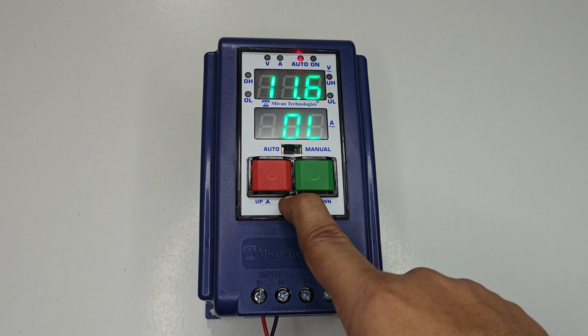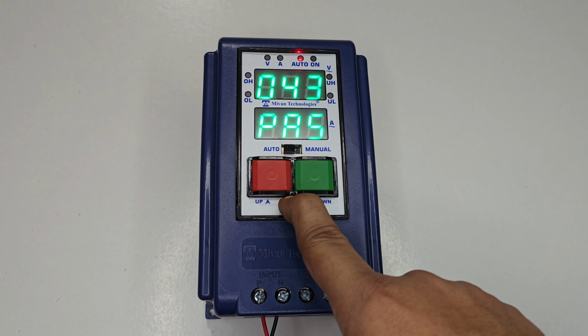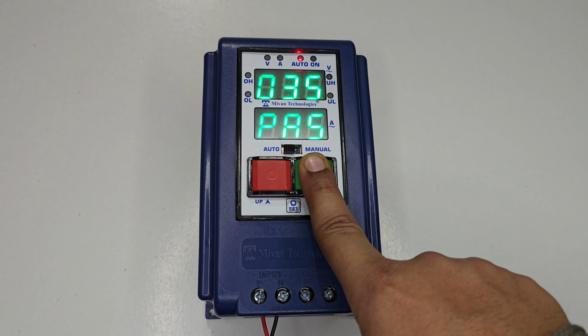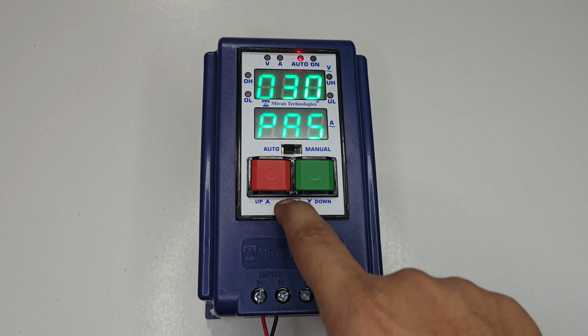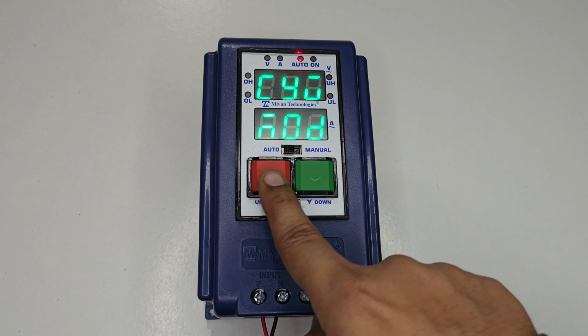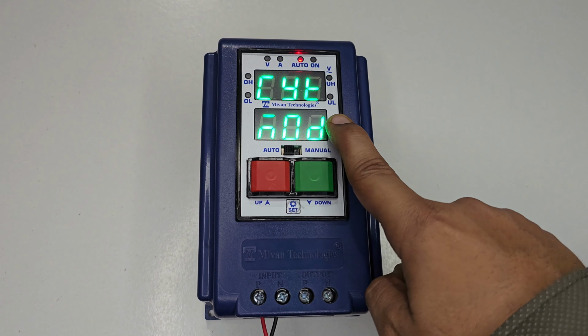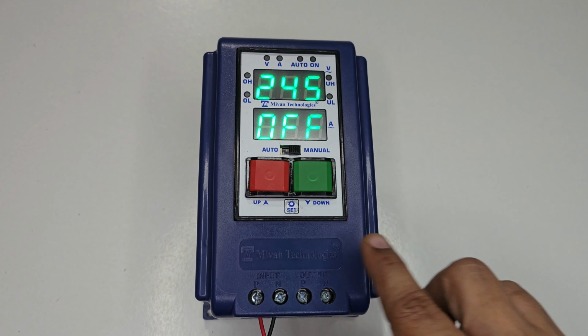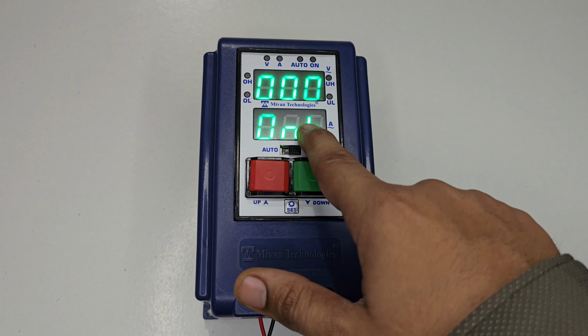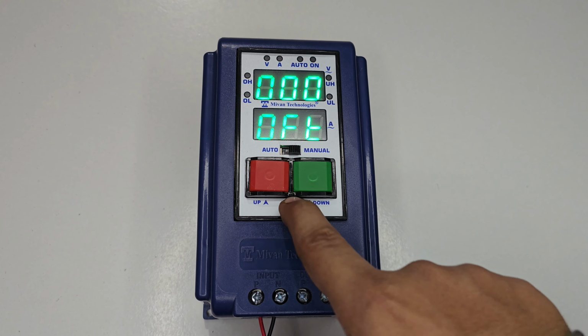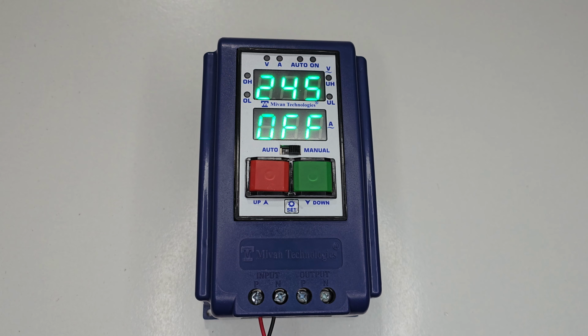Press the set button for 5 seconds. Again go to the password 30. Press the set button. Here in mode, if you select CYT mode, that timing mode works in manual mode. You put the device in manual mode. In manual mode, you can select the on timing, cyclic and off timing. So this cyclic timer works in manual mode and it is independent of the water controlling functions. So if you set 1 hour as on timing and 2 hour as off timing, then it continuously turns the motor on and off according to your on and off timing.